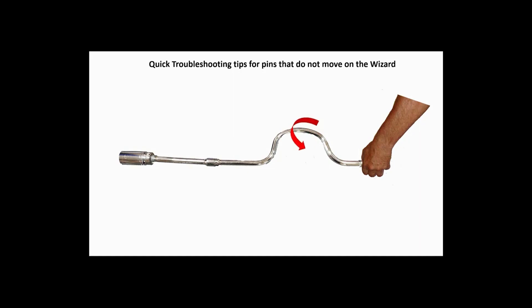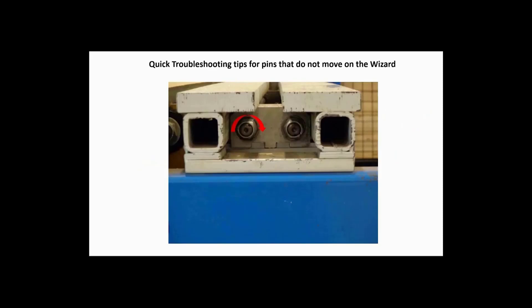So if the problem rail is trying to return itself, allow it to turn the speed wrench in a controlled manner. If the problem rail returns itself to the original position in one direction, then verify the same operation turning it in the opposite direction.